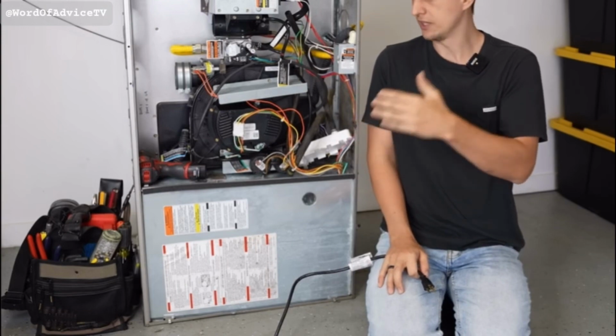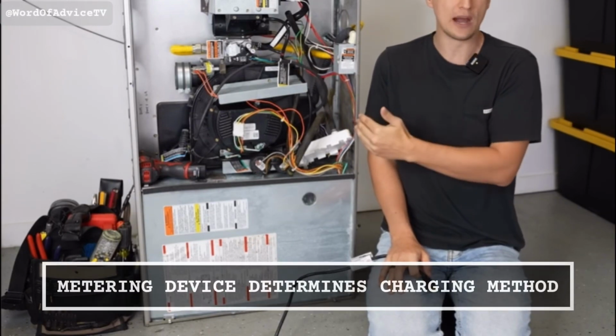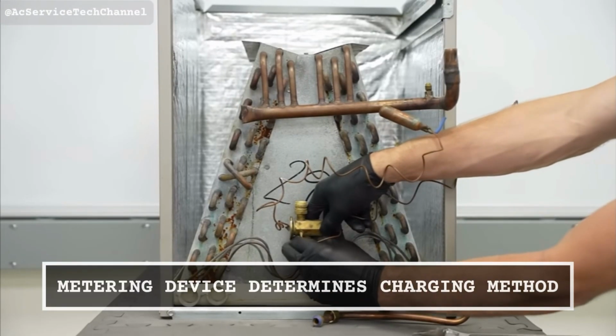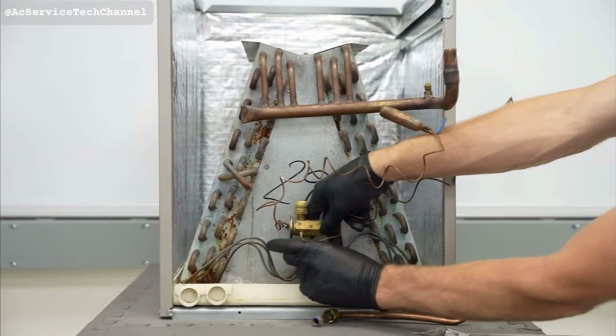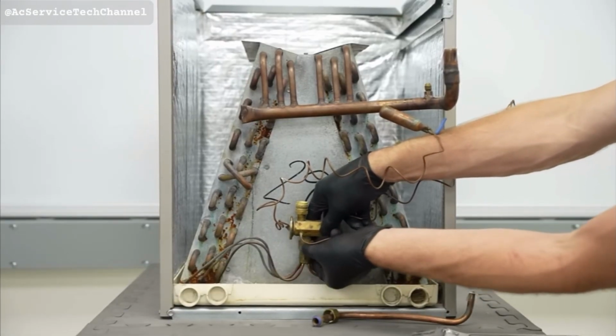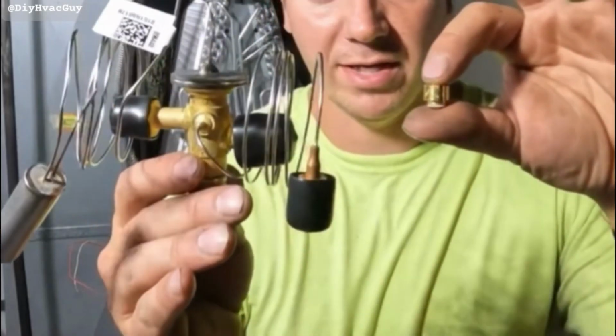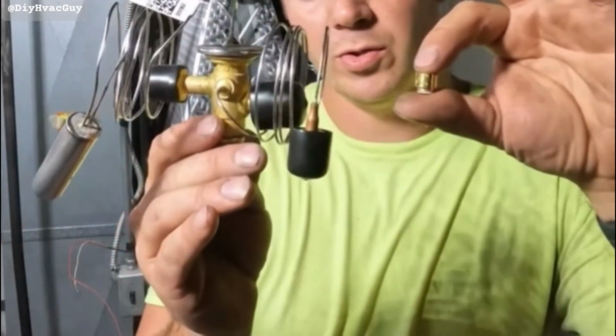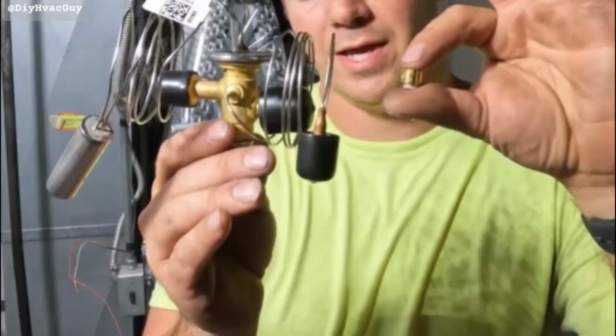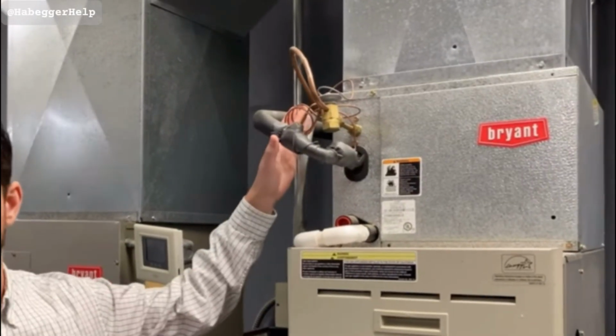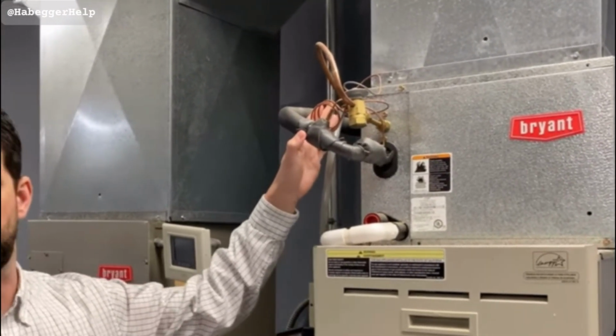Number 1. The metering device dictates the charging method. Inside your evaporator coil, there's either a thermal expansion valve, called a TXV, or a fixed orifice piston. The TXV automatically adjusts refrigerant flow as load changes. The piston doesn't, it flows a fixed amount. The charging procedure is different.